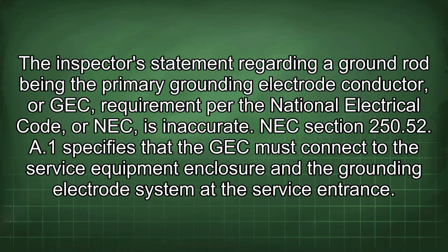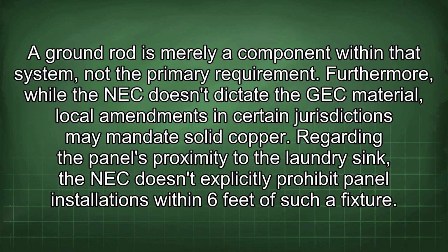The inspector's statement regarding a ground rod being the primary grounding electrode conductor, or GEC, requirement per the National Electrical Code, or NEC, is inaccurate. NEC Section 250.52 A1 specifies that the GEC must connect to the service equipment enclosure and the grounding electrode system at the service entrance. A ground rod is merely a component within that system, not the primary requirement.